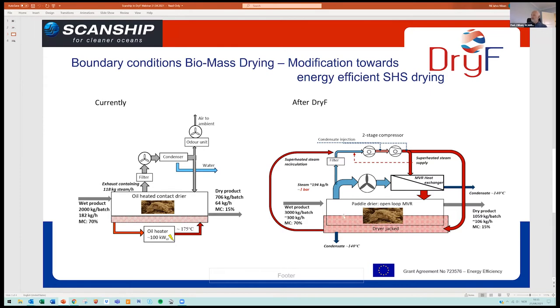So what we have done here, we have made now an indirect and a direct heat dryer, in the sense that we take the evaporated water from the biomass into the compressors and put it back again to recover the heat of condensation. And we put that to a heat exchanger in the circulation loop of steam, and we also put it in the heating jacket of the dryer. So it's a combined effort, and that has also shown to improve the efficiency and the capacity of the dryer with almost 100%, which is very good. So we are very happy with this. So it was a heavy design work and manufacturing work to provide the new dryers that really could utilize the superheated steam for the drying purposes.